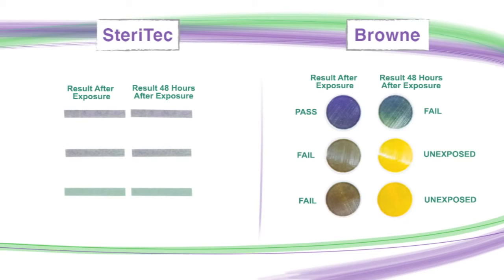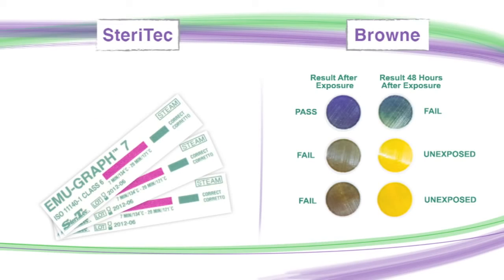If a patient infection were to occur and these records were inspected for proof of sterilization, the sterile processing professional would have apparently archived an insufficient or unexposed result, even though the color change was evident immediately after exposure. This would expose the healthcare facility to a wide variety of liabilities. As you can see, the SteriTec products remain as they did when initially archived. The indicators that demonstrated an insufficient result have not changed, and the pass result is still showing a complete purple to green color change. This is because the color change is clear, accurate, and permanent.